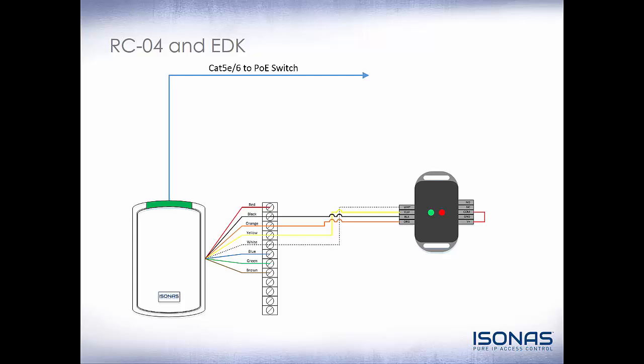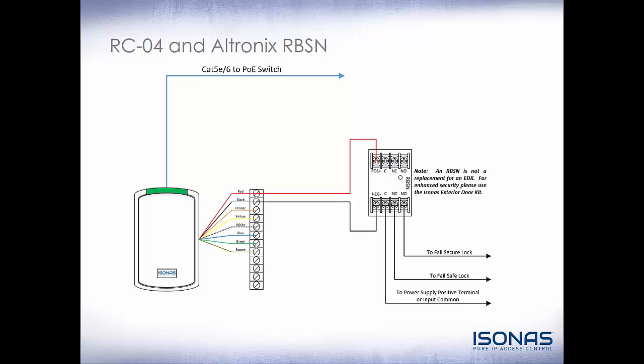We can see the connections here to the reader controller, similar to the RC-03. Orange and black are our static 12 volt DC power. Yellow and white is our communication to send a secure signal to the EDK to tell it to unlock the door. We can use an Altronix RBSN in lieu of the EDK, but please note the RBSN is not a direct replacement. For enhanced security, use the Isonas Exterior Door Kit. The RBSN simply detects voltage presence or absence to change relay state, whereas the EDK looks for a secure signal. The RBSN is connected to the red and black wires off the reader controller, and the lock ties to either the normally open side for fail-secure or the normally closed side for fail-safe.